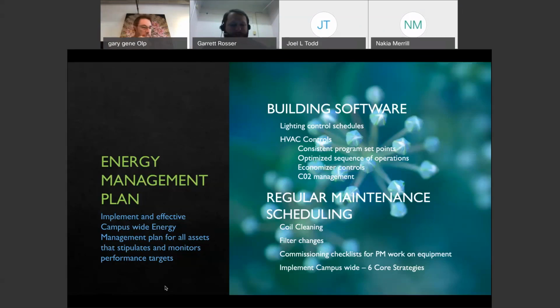Economizer controls. We already talked about the potentially negative impact of bringing in too much outside air. But a lot of folks miss out on the opportunity for economizing in North Texas because they say, oh, it's Texas, it's hot, it doesn't make sense to have economizers. Well, particularly for the institutional environment, we tend to have times, even in the winter, where we have higher heat load, whether that's equipment or a high number of bodies in an interior space. So with economizers, we still take advantage of hundreds of hours a year of free cooling.